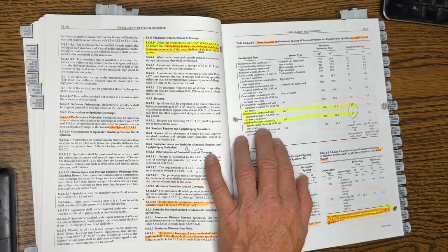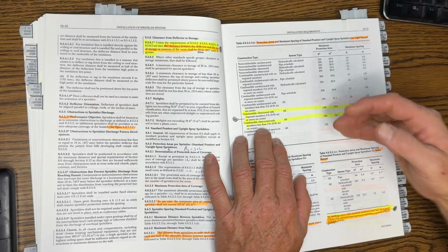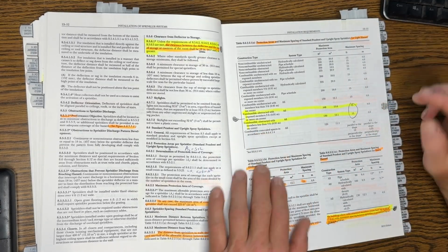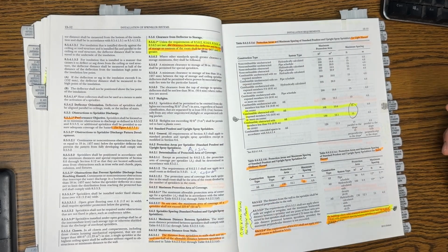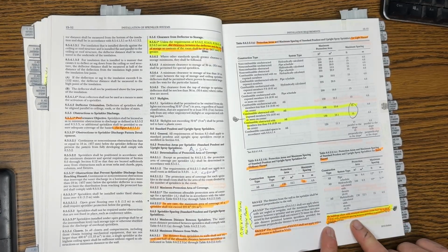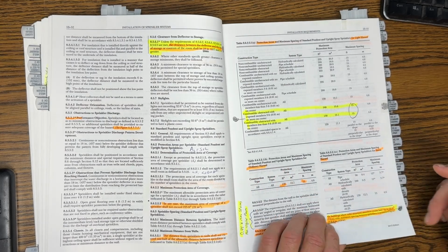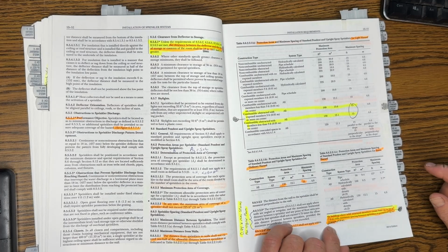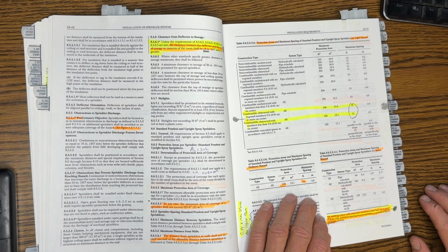Okay, let's see. What is the maximum spacing for sprinkler heads in a 20-foot wide extra hazard room, so EH? So you have light hazard, ordinary hazard, extra hazard, and then there's some storage occupancy. When you hear EH, it's extra hazard. So 8.6.2.2.1.C was what was used here. If you look at the footnote, up to 25 feet wide, sprinklers are permitted up to 12.5 feet between sprinklers. So the answer in this question was 12.5 feet maximum spacing for sprinkler heads in a 25-foot wide extra hazard room.